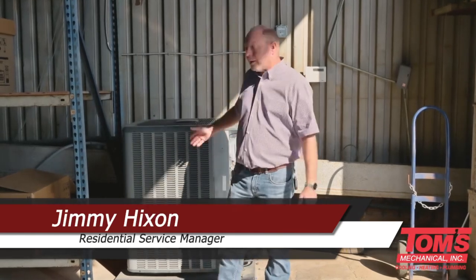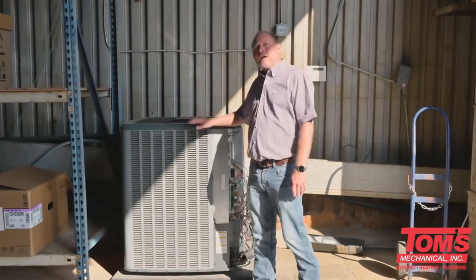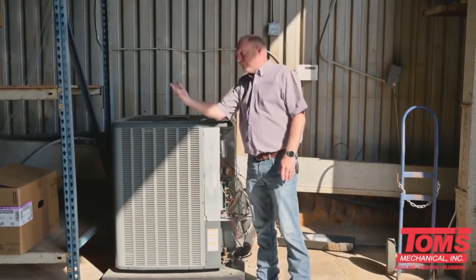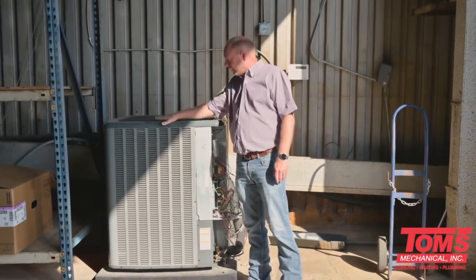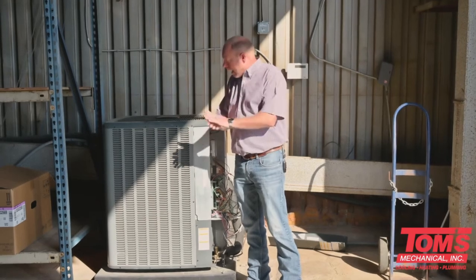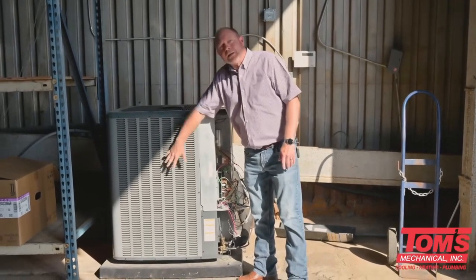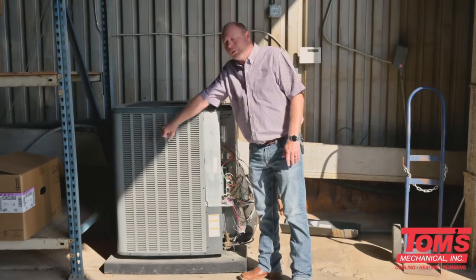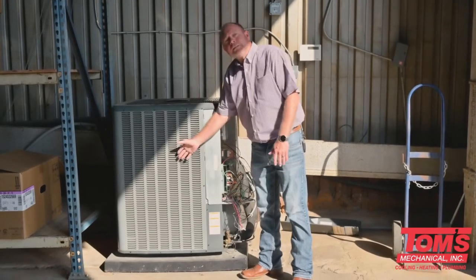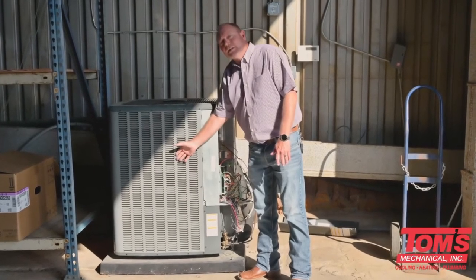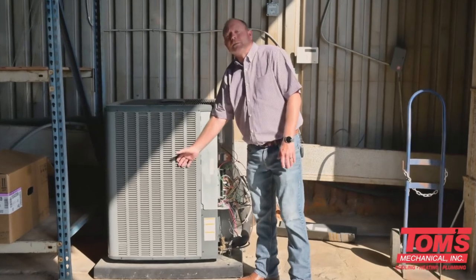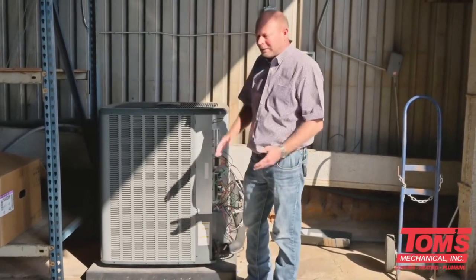Today I wanted to give you a glimpse into your system and talk about why maintenance is so important. Now here we have one of our training units in the warehouse here. As you can see, even in the warehouse, it gets fairly dirty. Your coils are in this area here. They go all the way around the unit. And it's very important to get these cleaned at least once a year, if not 2 or 3 times throughout the summer, depending on the environment that it sits in.